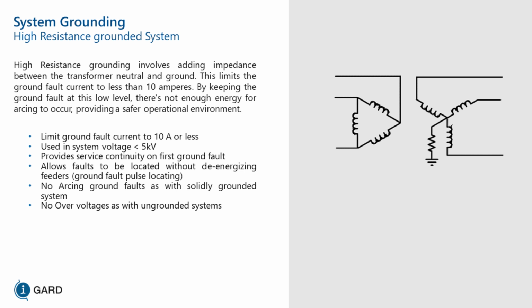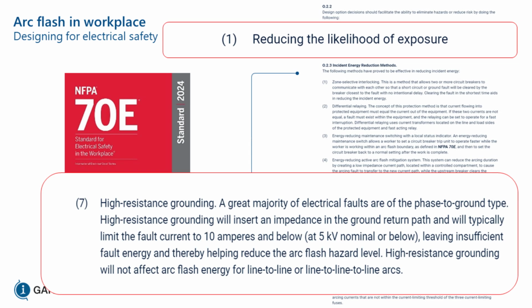And the NEC and CEC say that if you limit your fault current to a low value, CEC says 10 amps or less, NEC says a low value, and you look at 250.36 in the NEC or 10-300 in the CEC, that is the Canadian Electrical Code, all systems 5 kV or less provide service continuity. So this is for facilities that can't tolerate outages for a ground fault. On one hand, we have a solidly grounded system, where you have a ground fault and you have to trip by code. On the other hand, we have a high resistance grounded system. The same ground fault allows you to keep running, and we provide you with the tools to look for the ground fault.